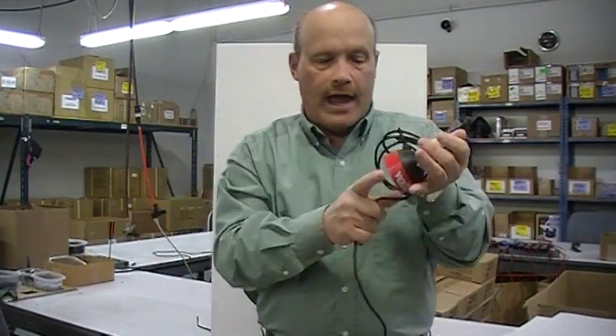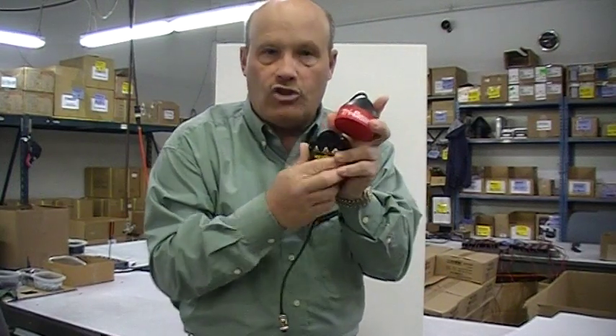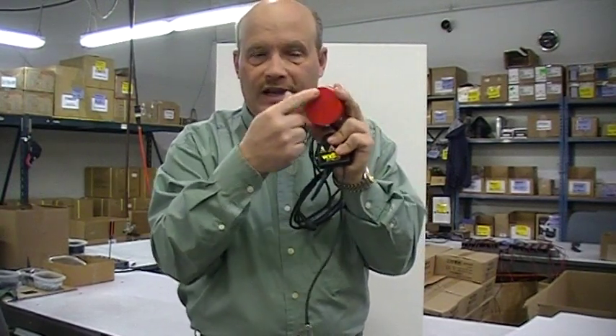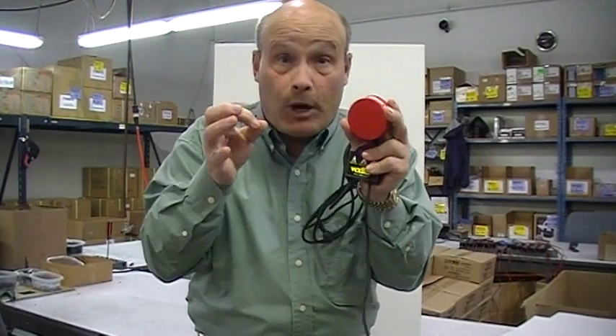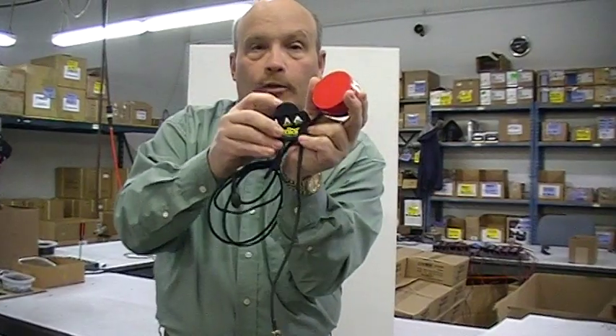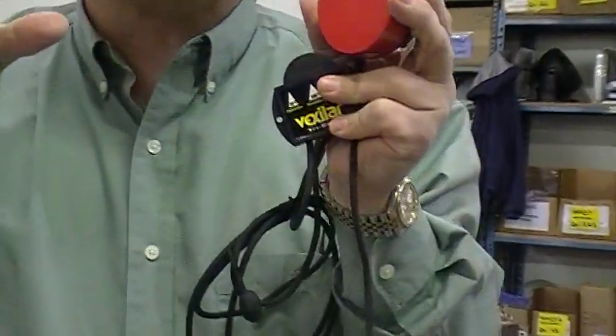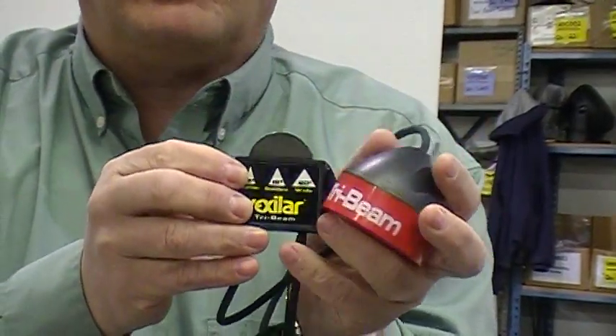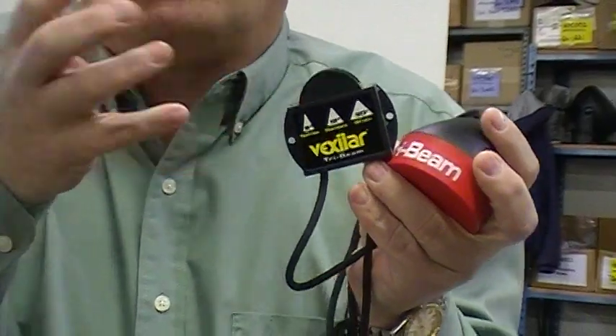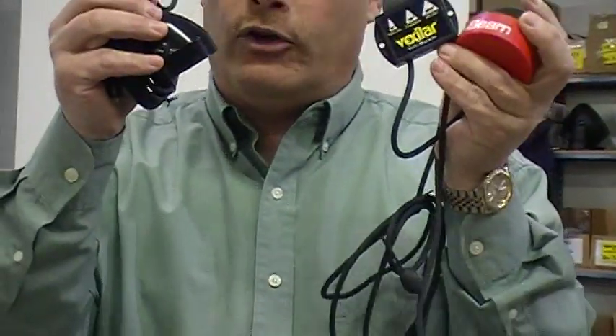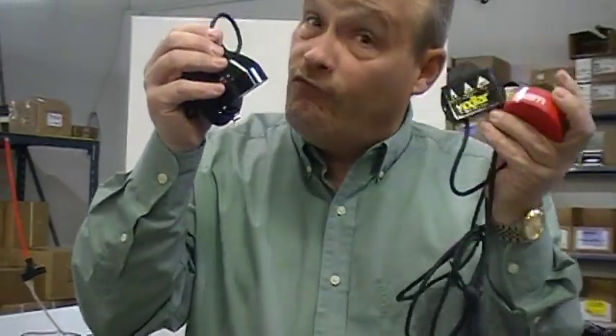The Tri-Beam, on the other hand, offers a mechanical opportunity to adjust it. Now, we do it with multiple crystals in this array, that it gives you the same type of impression. By simply going from a switch from 8 to 12 to 20, you can go from narrow, medium, to wide. In my opinion, that's a much more practical way of looking at it. The narrow, medium to wide perspective in a mechanical form is how the Tri-Beam works, and it works extremely well. So when people say, what are the differences between the ProView and the Tri-Beam, in many ways they function very similarly, except the fact that the ProView gives you almost an unlimited range of area you want to hear.